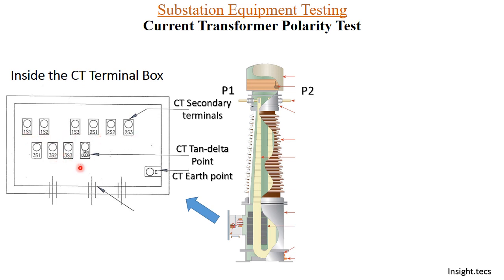The CT shown here is a dual ratio CT. It is identified because each coil has three terminals: 1S1, 1S2, and 1S3. Similarly for 2S: 2S1, 2S2, 2S3, and the same for 3S. There is also a CT tan delta point and CT earth point given here.